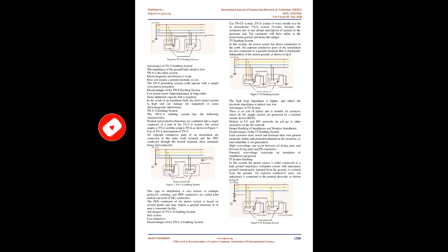All exposed conductive parts of the installation are also connected to a ground electrode that is electrically independent. Figure 8, TT earthing system. The fault loop impedance is higher, unless the electrode impedance is indeed very low. Advantages of TT system. There is no risk of failure and it is suitable for premises where all AC supply circuits are protected by a residual current device, RCD.